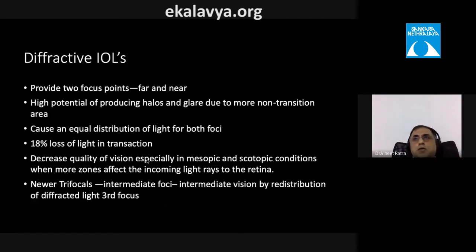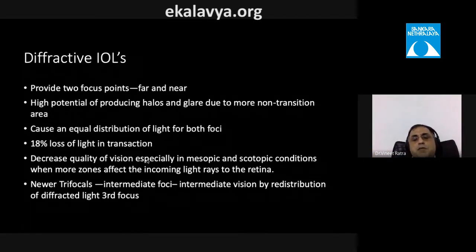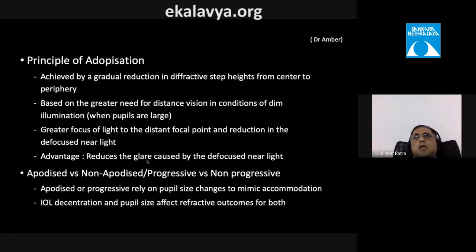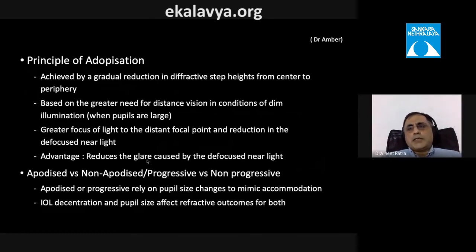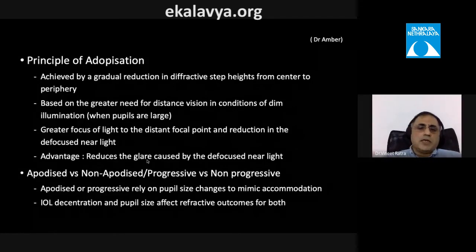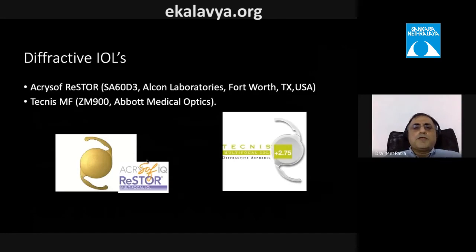Newer trifocals like the PanOptix work on the diffractive platform and incorporate an intermediate focus for a third focal point. Apodization — used in Alcon's technology — involves a gradual reduction in diffractive step height from center to periphery, reducing glare and halos associated with near diffractive rings.